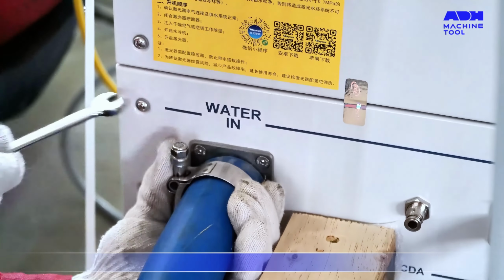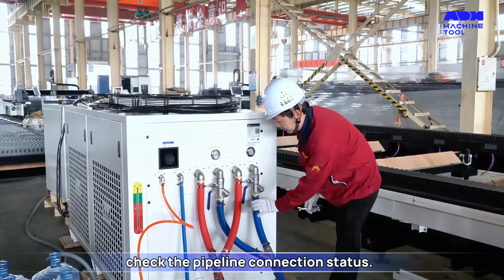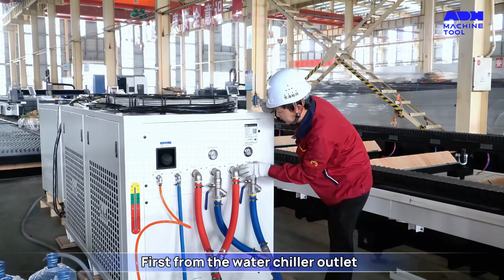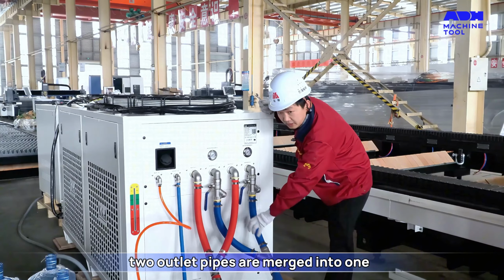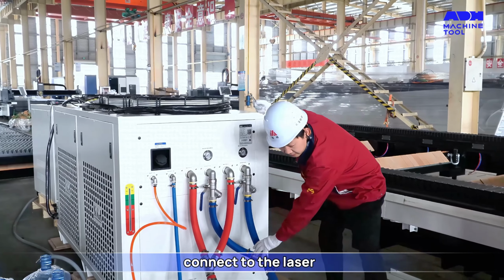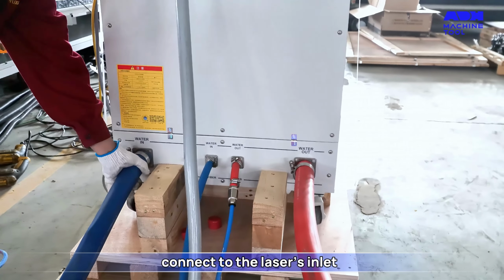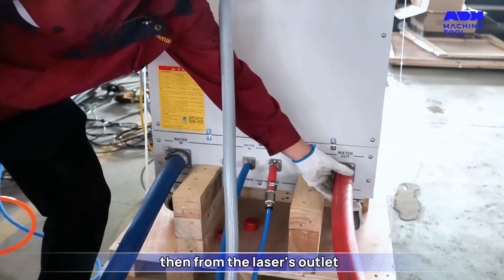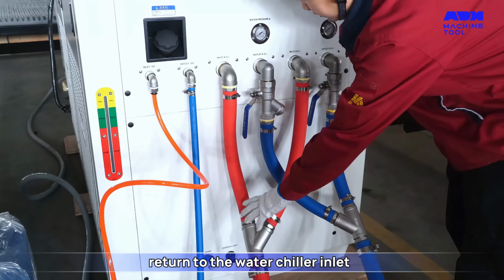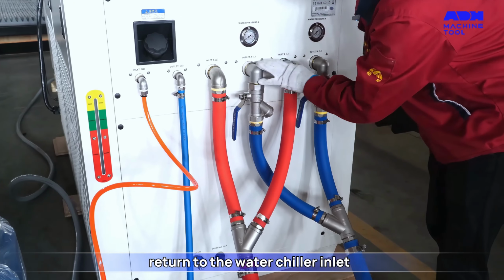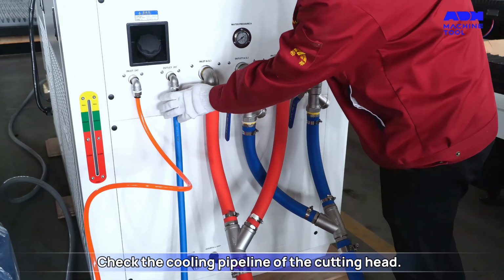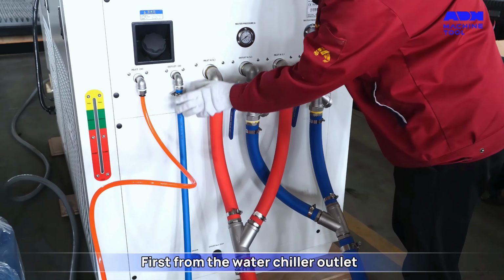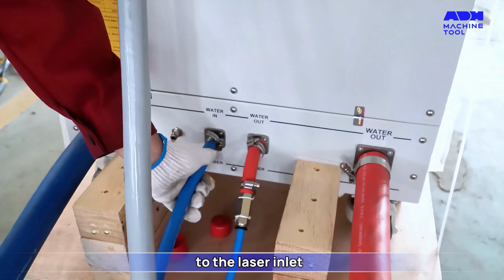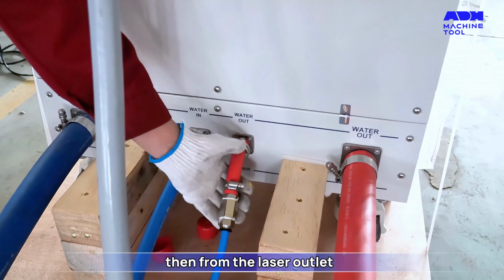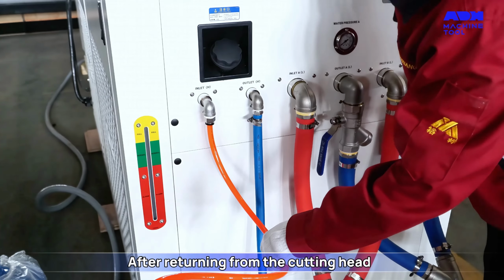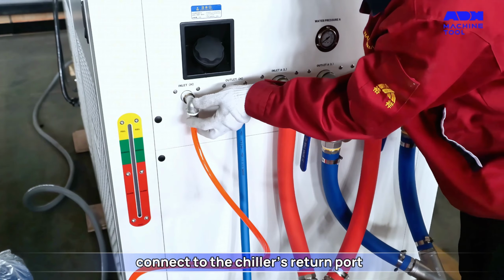After checking the clamp tightness, check the pipeline connection status. First, from the water chiller outlet, two outlet pipes are merged into one, forming a single pipeline. Connect to the laser's inlet. Then from the laser's outlet, return to the water chiller inlet. Check the cooling pipeline of the cutting head. First, from the water chiller outlet to the laser inlet, then from the laser outlet to cool the laser cutting head. After returning from the cutting head, connect to the chiller's return port.